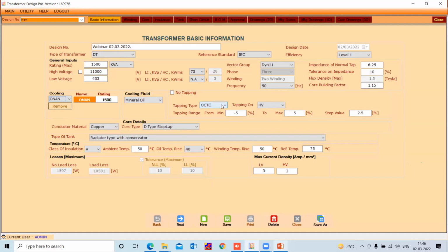Then you have the tapping. You can go for the tapping, whatever you wish. We're talking about the OCTC. OCTC is nothing but off-circuit tap changer. It is unlike OLTC. OLTC is on-load tap changer. So let's select any one and go for the tapping on HV that you have chosen here, -5% to +5%. You can set whatever you wish. You can set the step value. Here you have chosen it to be 2.5. -5 to +5 with a step value of 2.5 will mean there are about 5 taps here.